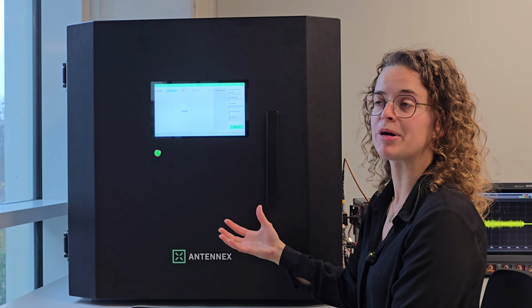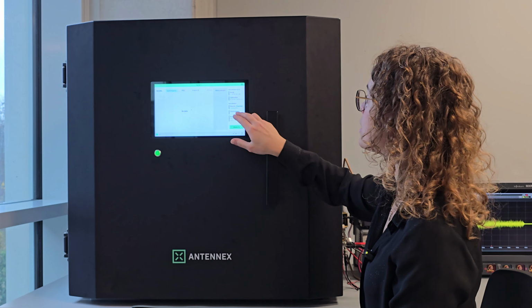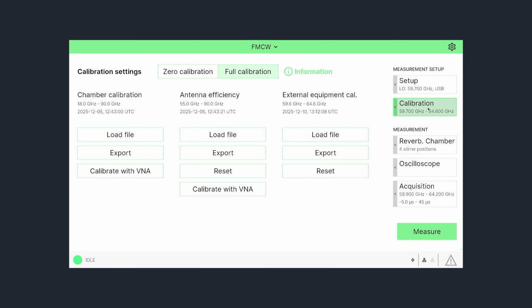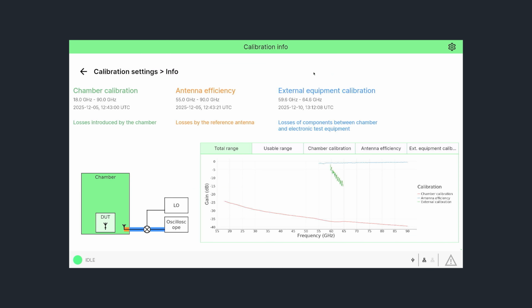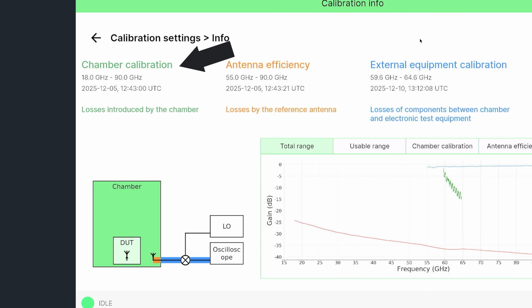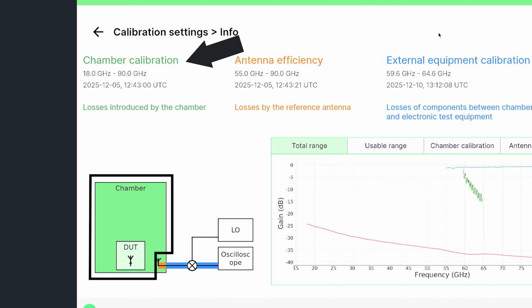Before we can do a measurement, we have to do a calibration. And this you can access via the calibration menu. In the calibration menu, you will see that there are three parts of the calibration, which are the chamber calibration, the antenna efficiency, and the external equipment calibration. And what these three factors mean, you can see in the information section. So you can see that the green part, that is the chamber calibration. That is the losses in the chamber itself, including the DUT loading.